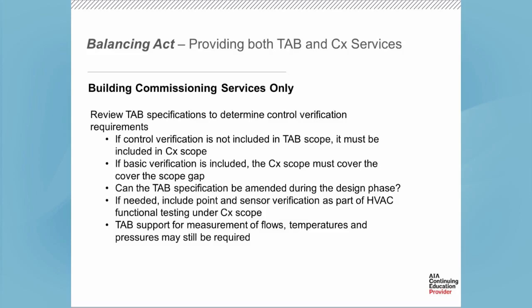That's one piece that could get overlooked in both scopes. If the tab spec doesn't require it, and you have a commissioning provider that may not traditionally go out and verify actual point and sensor calibration, or even require the controls contractor or the mechanical contractor to demonstrate that, it could get overlooked, and that's a very important step in the process.